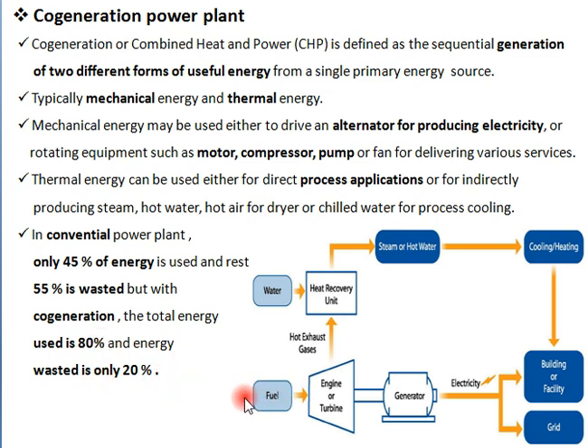In a co-generation plant, we can utilize the flue gases further to increase the temperature of water, convert it into steam, and use that steam or hot water for different purposes. In total, 80 percent of the energy from the flue gases can be utilized — first mechanically, then thermally — and only 20 percent is wasted. This gives much more efficiency from the plant.